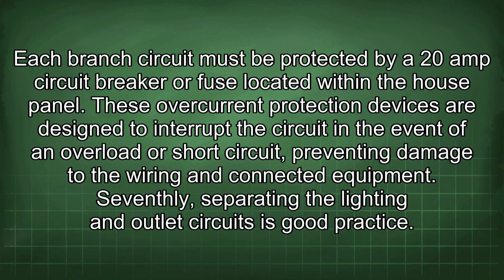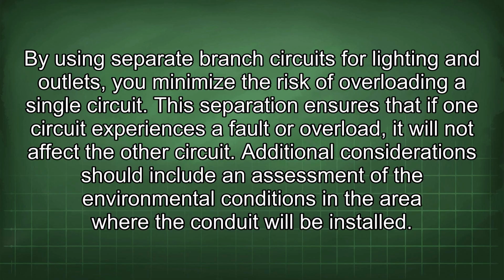Seventhly, separating the lighting and outlet circuits is good practice. By using separate branch circuits for lighting and outlets, you minimize the risk of overloading a single circuit. This separation ensures that if one circuit experiences a fault or overload, it will not affect the other circuit.